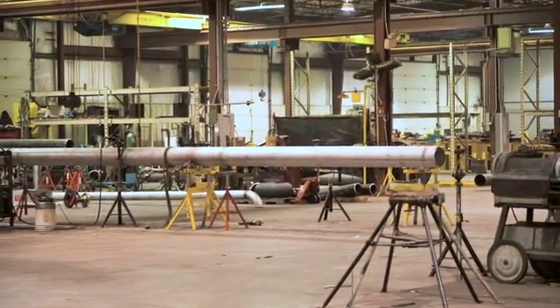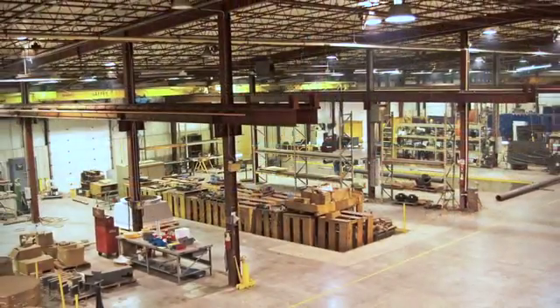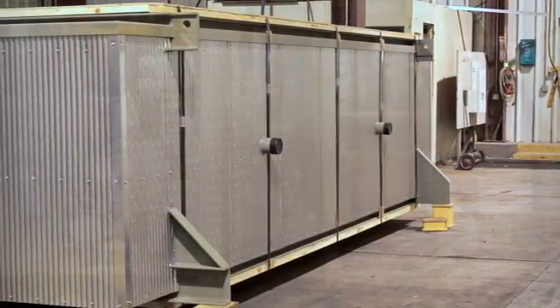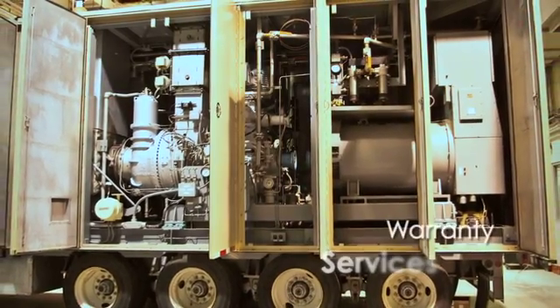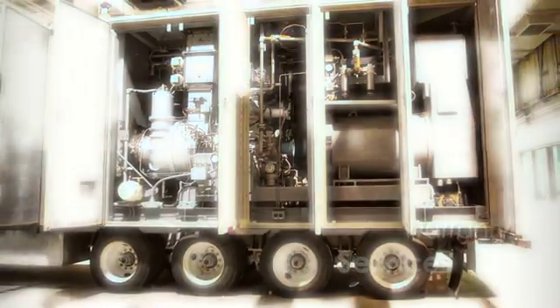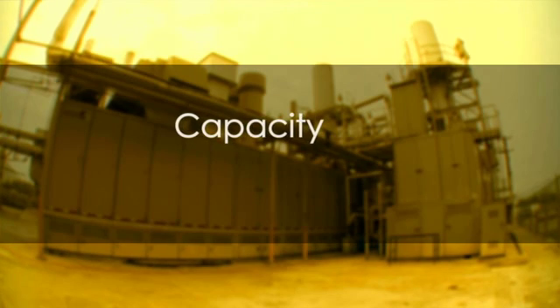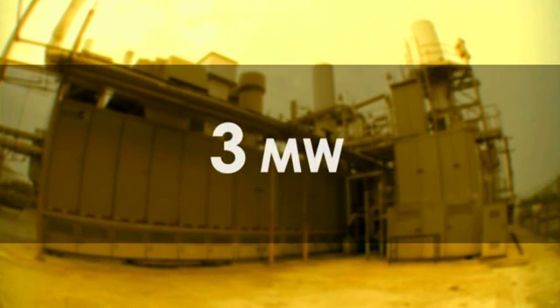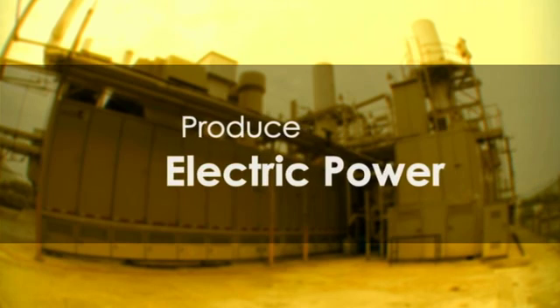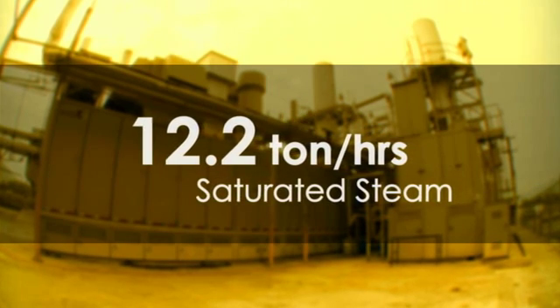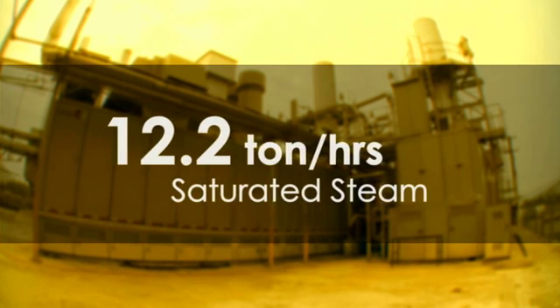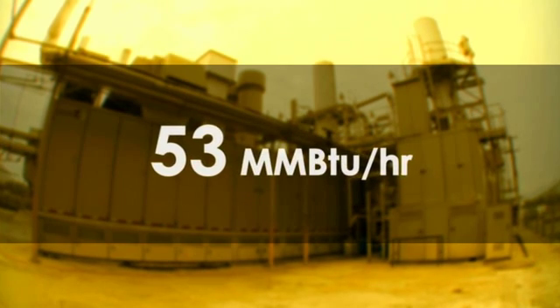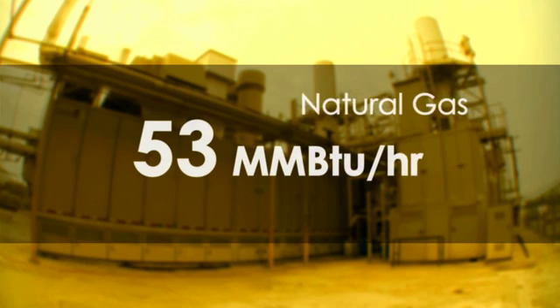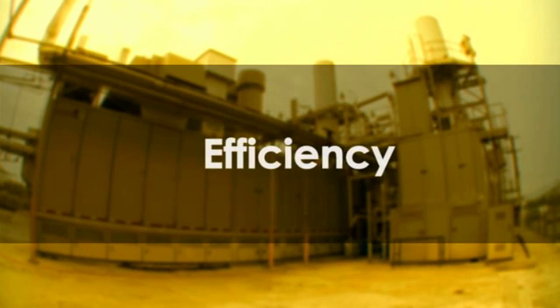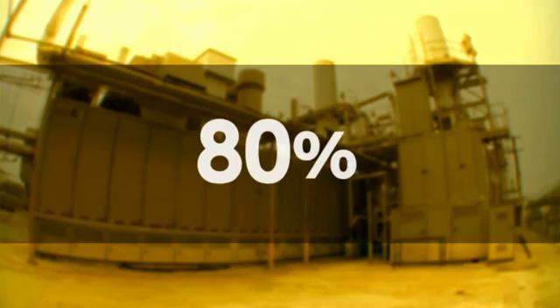They are assembled, tested, and certified in our AGC plant. The units fulfill and exceed the highest manufacturing and quality standards, providing our users an excellent warranty of our services. At nominal capacity under ISO conditions, the MCUs can produce 3 megawatts of electric power and approximately 12.2 tons per hour of saturated steam. Basic energy input is about 53 million BTUs per hour from natural gas or diesel. The cogeneration system is able to reach efficiency around 80%.